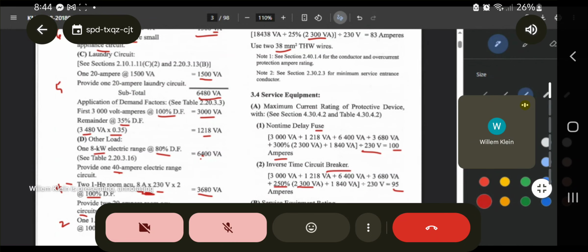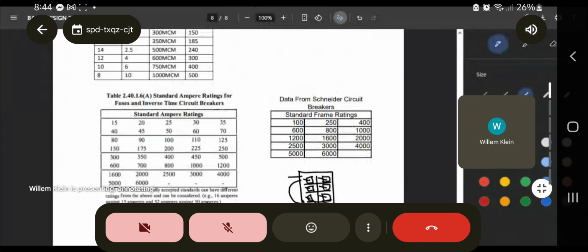on the circuit breaker part here, so let's proceed on the table here. So they use 125. Okay. Ito nga. So, di ba, they computed for 95 amperes. So the 95 amperes falls within 100, 110, 125. So they selected 125.